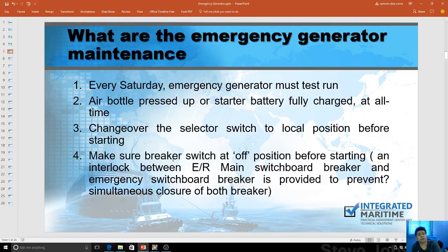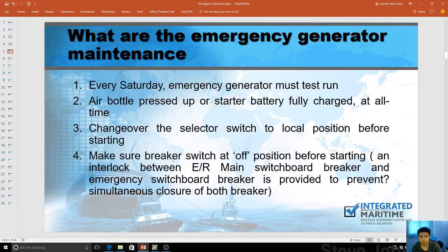Emergency generators are tested every Saturday. On board, we test them every Saturday. Before arrival, there's a 12-hour requirement from Regulation 26, Chapter 5, where you start the steering gear, emergency equipment, and everything. The air bottle or starter bottle must be charged at all times — checked daily by the electrician during watch. You also change over the selector switch to local, and ensure the breaker interlock between the engine room switchboard prevents simultaneous closure of both breakers.